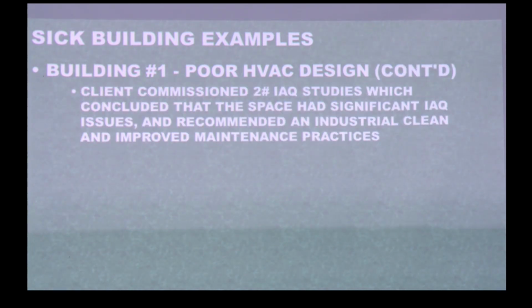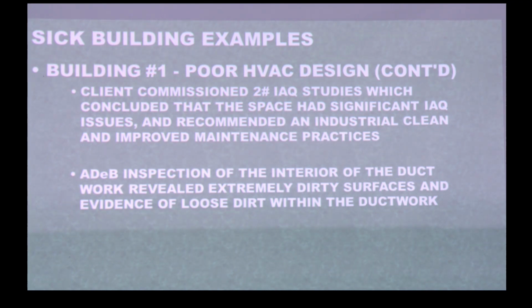Two indoor air quality studies were done, and they concluded that there were significant IAQ issues and recommended industrial clean and improved maintenance practices. Now this building was between 15 to 20 years old. We inspected the ductwork because part of our commission was to redesign a space and then investigate what the issues might be in terms of the indoor air quality. So we found some very dirty interior surfaces. When I say dirty, I use that word sparingly, as you'll see in the next photograph.